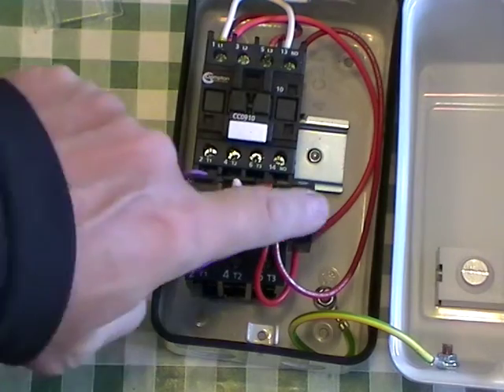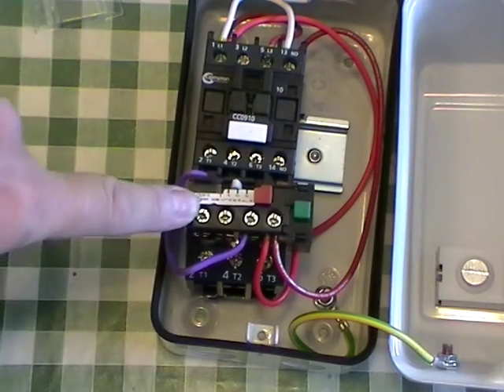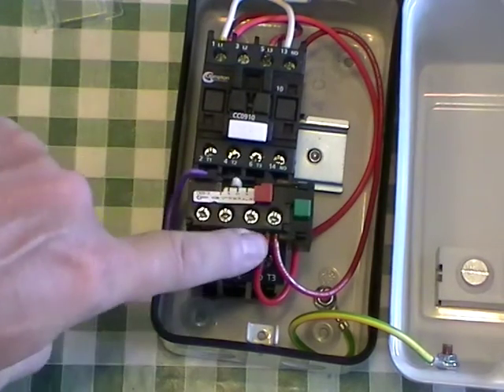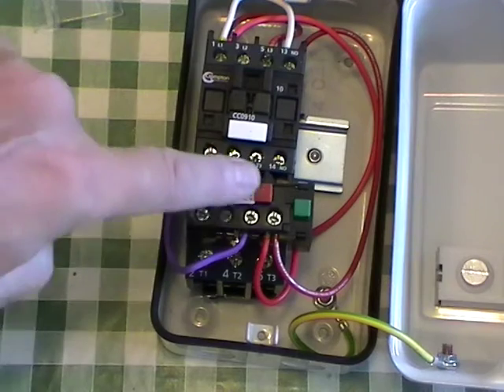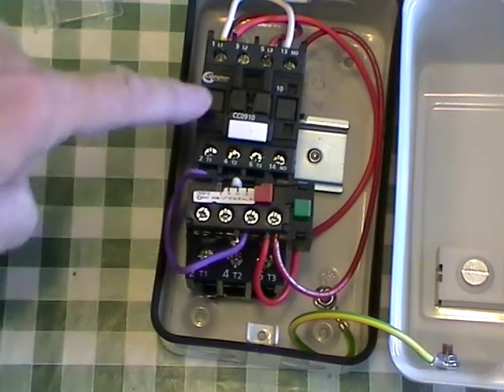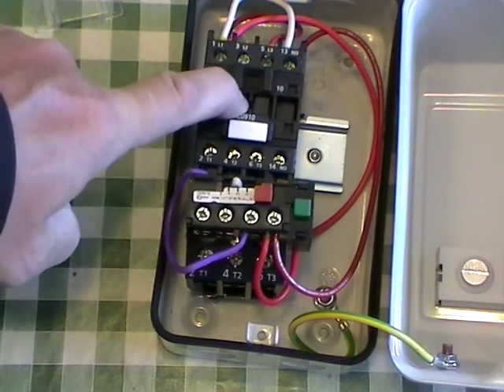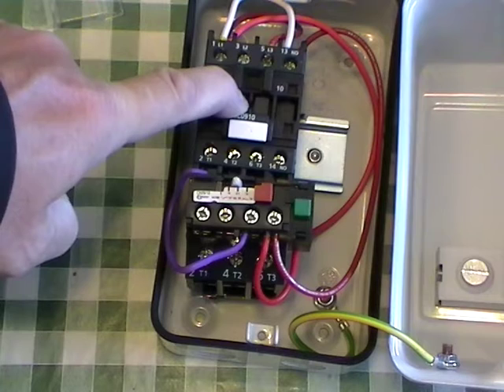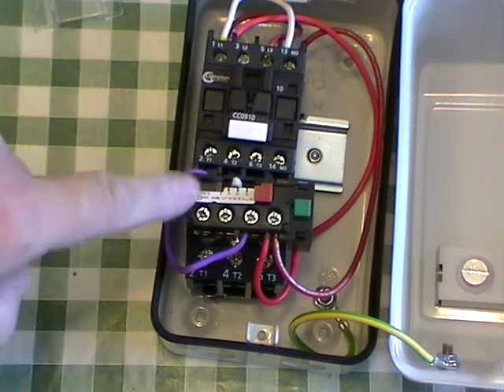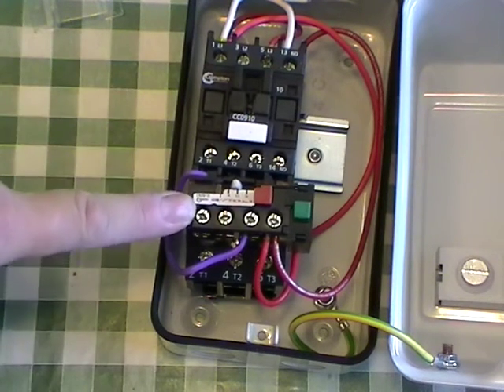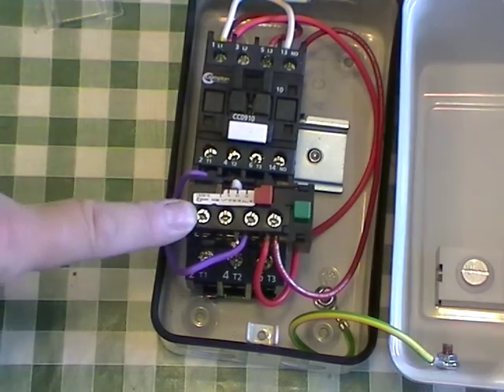But once the green button is released, the trip is in circuit for holding the contactor down, and the motor continues to be switched on. In other words, the green button will override the trip, but in normal use the trip will function as designed.